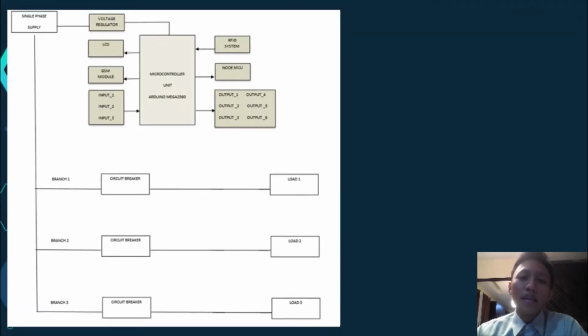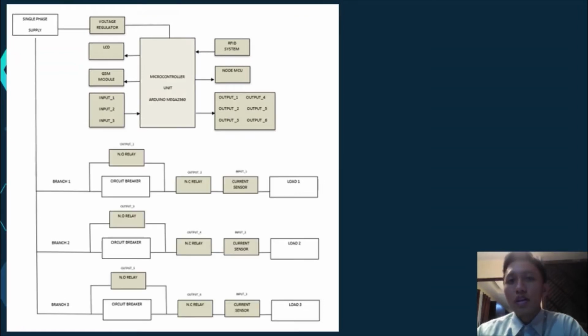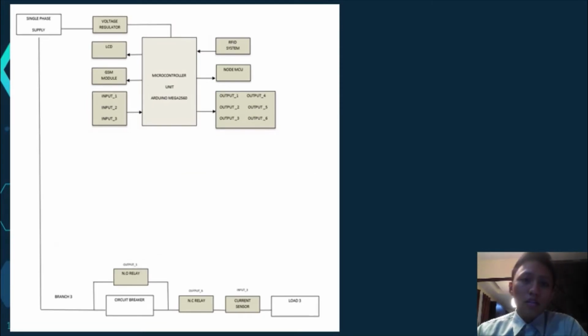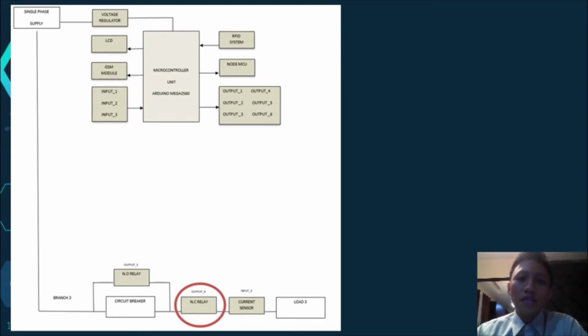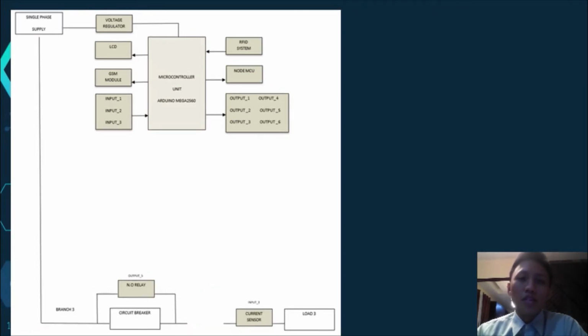So to address this problem, we have added access control into the circuit breaker by using microcontroller, RFID, and relays. To explain this concept in a simple manner, we will just be using one branch because in the prototype, this concept of access control actually works the same or similar with the other branches. As you can see in the figure, there is a normally closed relay connected in series with the load. When activated, the contacts of this relay should switch, thus causing an open circuit. So by this concept, we can turn off the power supply in a branch for an indefinite time as long as the normally closed relay is activated.